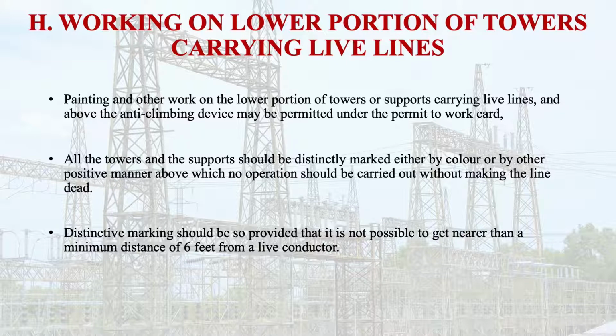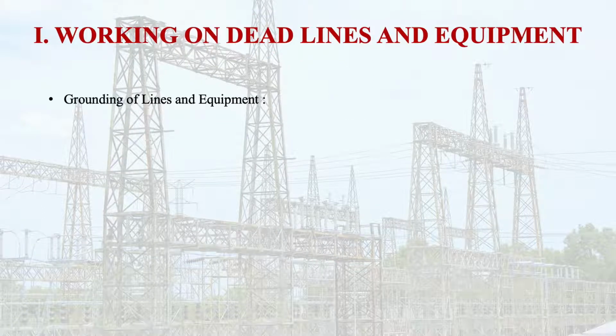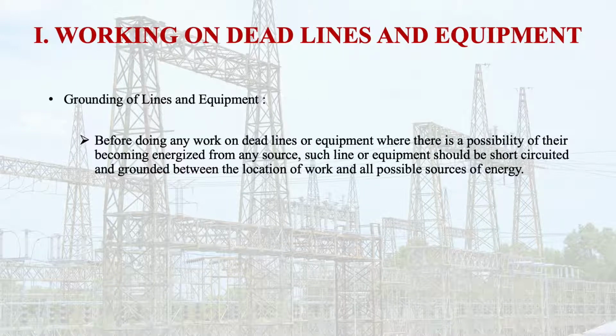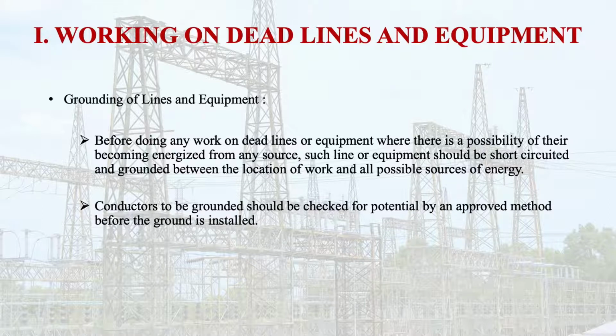Now let us discuss working on dead lines and equipment. So what are the safety instructions associated with this? Grounding of lines and equipment. Before doing any work on dead lines or equipment where there is a possibility of them becoming energized from any source, such lines or equipment should be short circuited and grounded between the location of work and all possible sources of energy. So conductors to be grounded should be checked for potential by an approved method before the ground is installed.